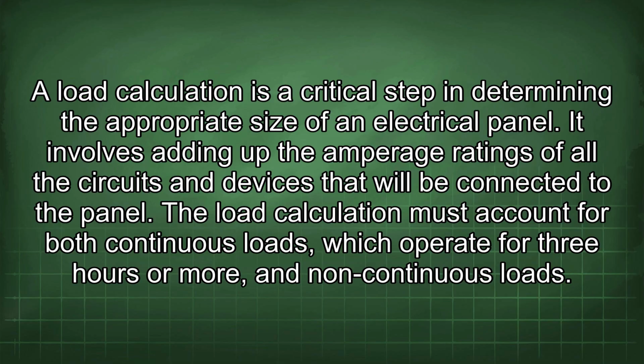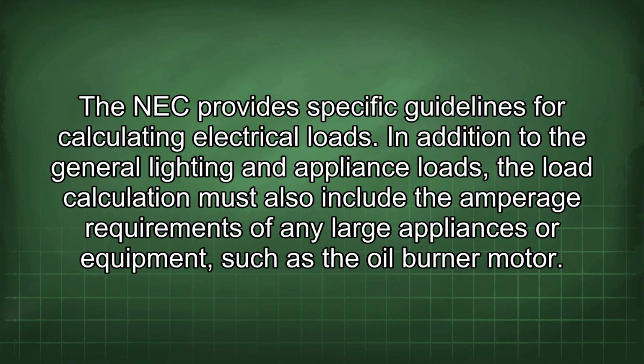It involves adding up the amperage ratings of all the circuits and devices that will be connected to the panel. The load calculation must account for both continuous loads, which operate for 3 hours or more, and non-continuous loads. The NEC provides specific guidelines for calculating electrical loads. In addition to the general lighting and appliance loads, the load calculation must also include the amperage requirements of any large appliances or equipment, such as the oil burner motor.